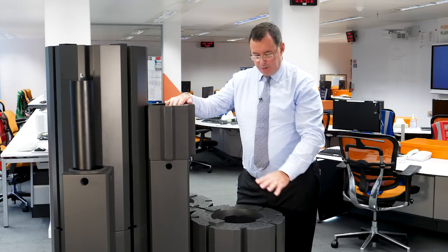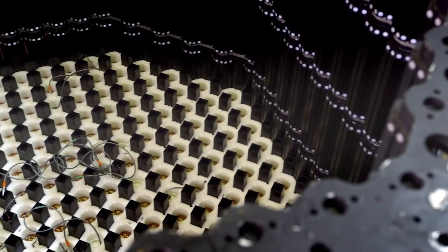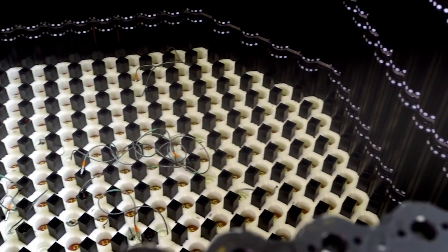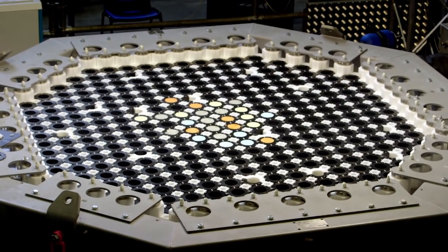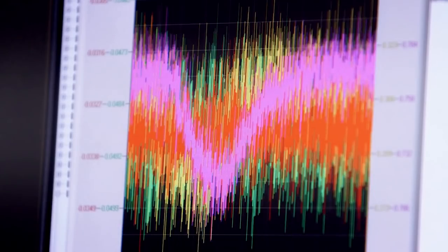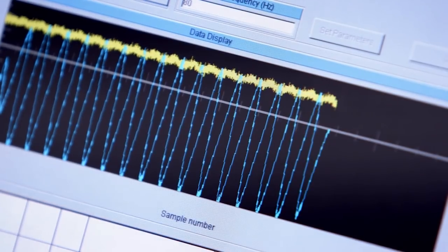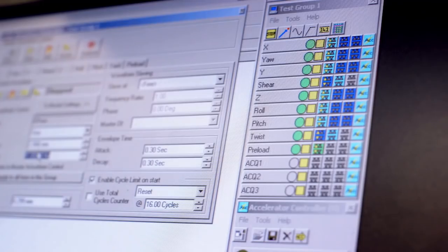So how can we be confident in what we've done? Well, one example is we've built a quarter scale model of this core and put it on a shaker table and subjected it to the earthquake. And we've measured the distortions and shown they were really quite small, even with lots of cracked bricks. We've also done some computer analysis to understand what's going on, and that modelling and that experiment gives us the confidence we understand the state of the core.